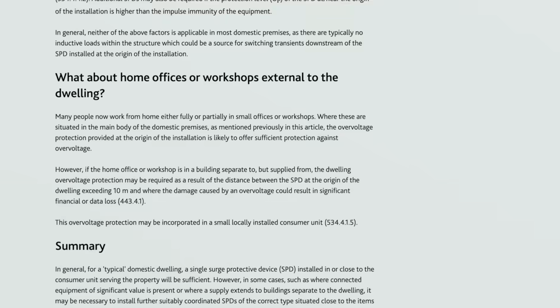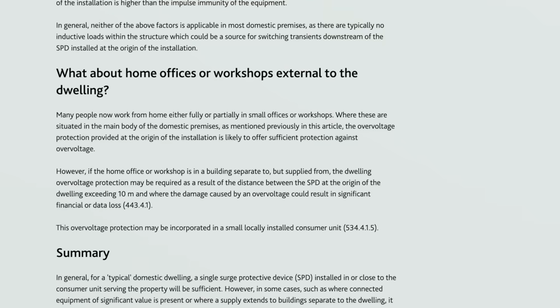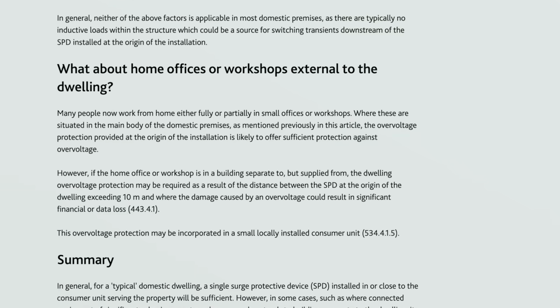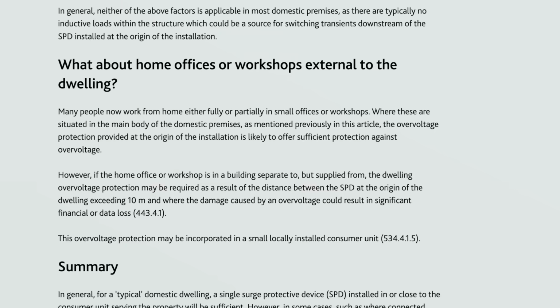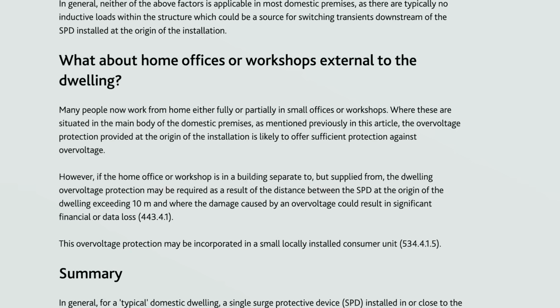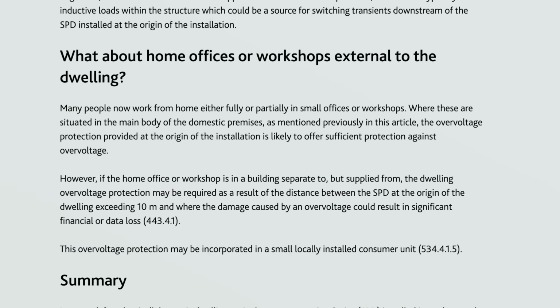The NIC says that in the example of a home office more than 10 metres from the main house, a separate SPD should be installed to prevent damage to computers and data loss. It recommends that the additional SPDs are housed in small local consumer units.